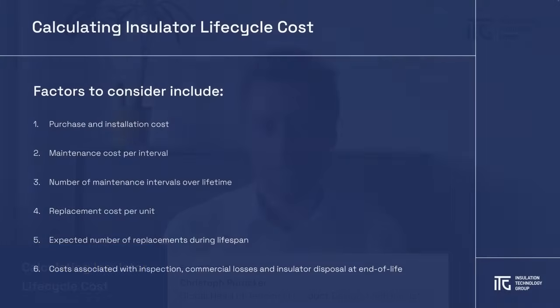Factors to consider include: purchase and installation cost, maintenance cost per interval, number of maintenance intervals over lifetime, replacement cost per unit, expected number of replacements during lifespan, and costs associated with inspection, commercial losses, and insulator disposal at the end of life.